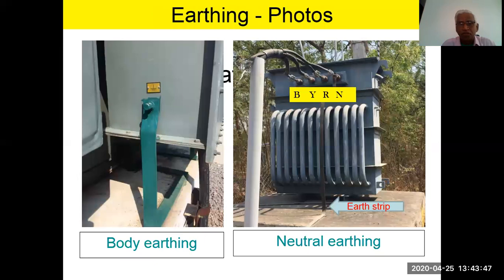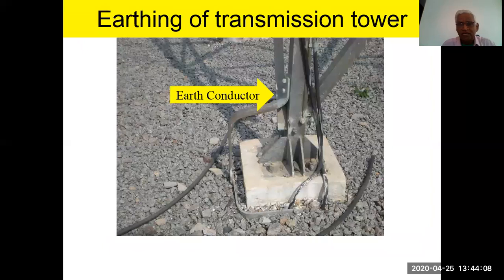And you can see in these photographs, the left side photograph shows that the earthing is connected to the body of an electrical equipment. On the right side, the earthing is connected to the neutral and taken into the ground through an earth strip. This is a distribution transformer of 315 kVA. And this is an earthing of a transmission tower. And you can see the earth conductor, the size of which depends on the fault level in the substation.